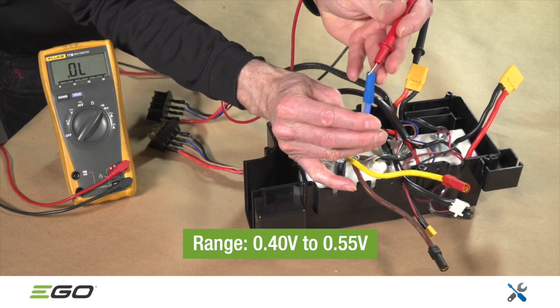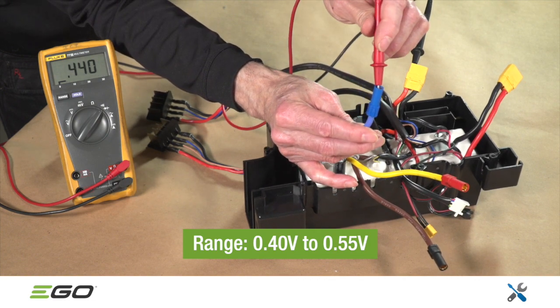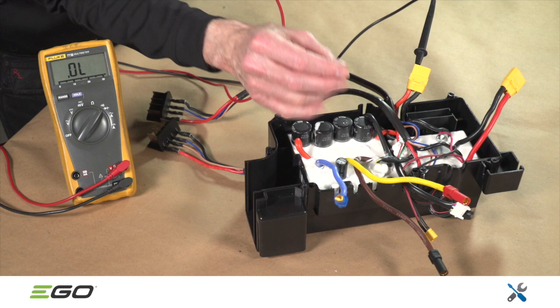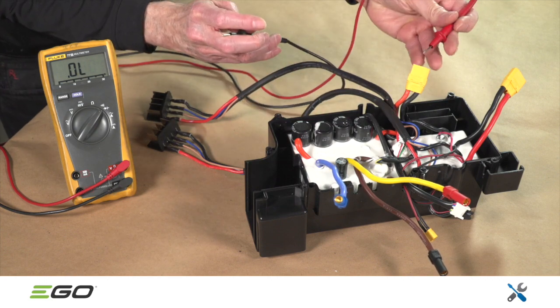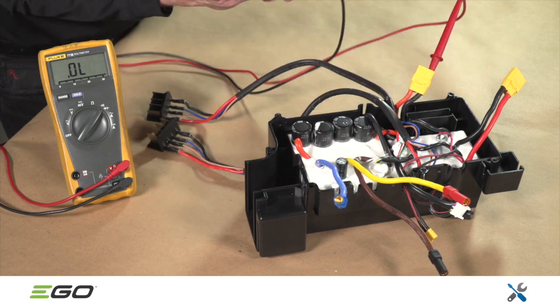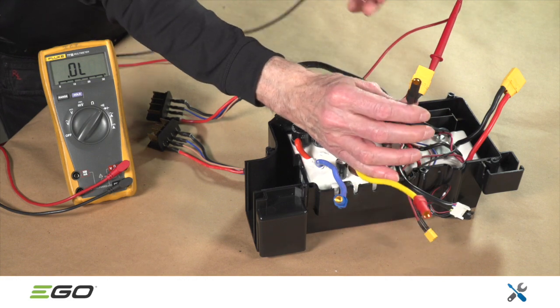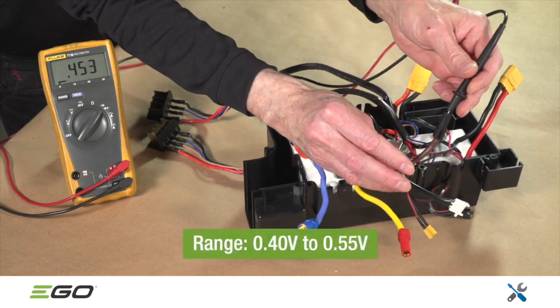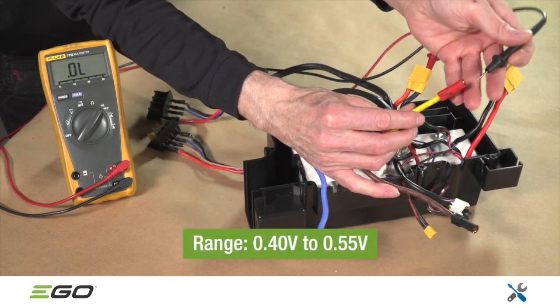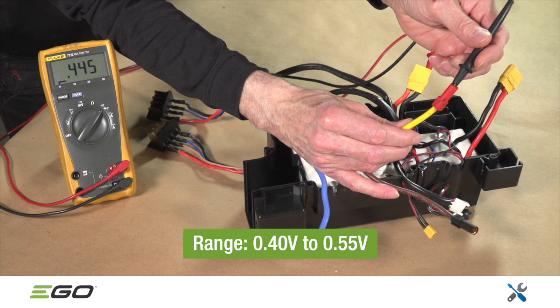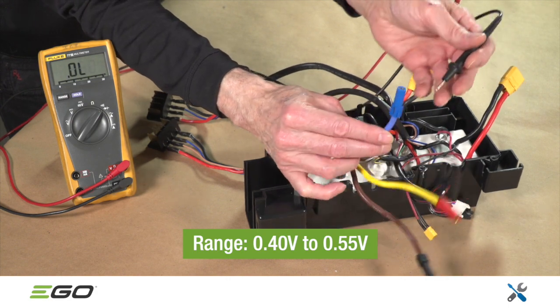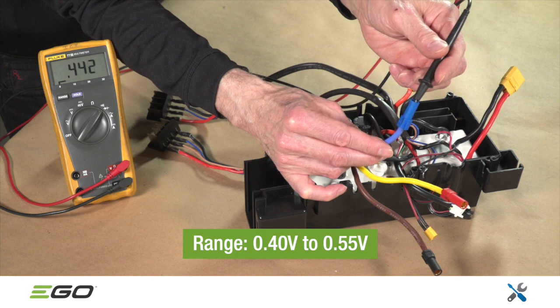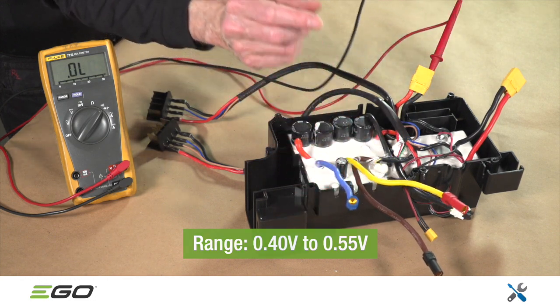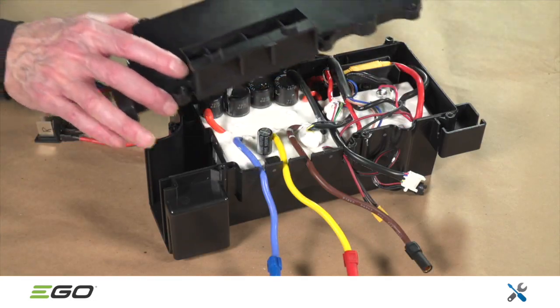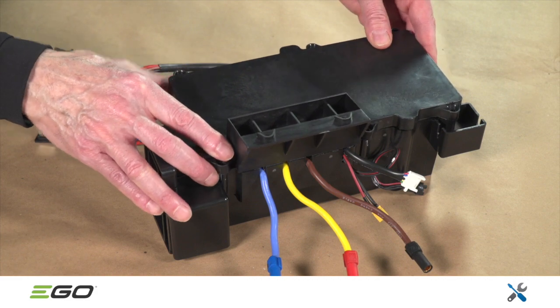be replaced. If all readings are within range, continue by touching the red lead from the multimeter to the black input and touch the black pin to the blue, yellow, and brown motor wires one at a time. Here again, if any reading is out of range, the control box needs to be replaced. If all measurements from the negative and positive sides of the circuit are good, the issue is in the handle. Replace the cover on the control box, making sure the wires are properly routed.